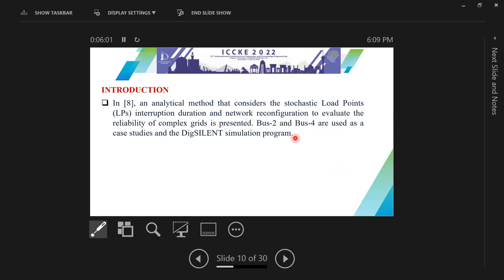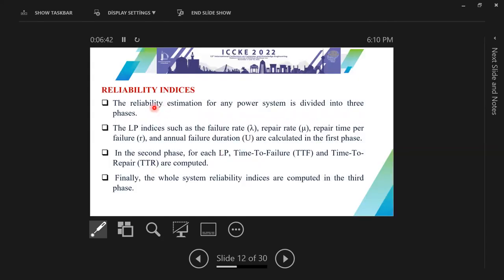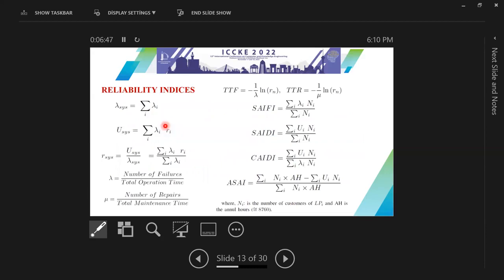BUS2 and BUS4 are used to conduct this analysis using DIgSILENT simulation software. In order to calculate the reliability indices, we first calculate load point indices — failure rate, repair rate, and annual failure duration. In the second phase, we calculate time to failure and time to repair. Finally, we compute the reliability indices for the overall system. The formulas for load point indices, time to failure, time to repair, and widely used reliability indices are provided.